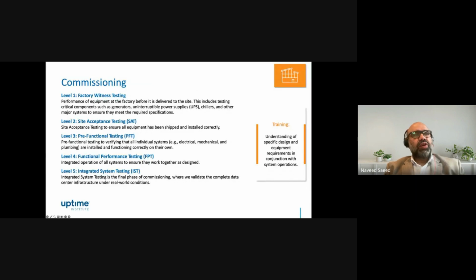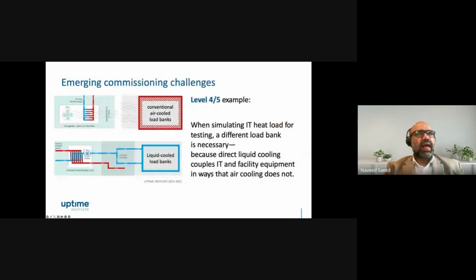Commissioning of these data centers, or recommissioning of a repurposed, retrofitted or upgraded facility, will be different from what we have been doing historically in data centers. So the five levels of commissioning are going to remain the same, but what is required to make it happen will change. For example, for level 4, level 5 commissioning, conventionally air-cooled load banks, as you can see on the diagram above here, were fitted into the racks or on the floor, and they take the cold air from the CRAC units or fan wall units and push the hot air back into the hot aisle containment or hot aisle plenum, returning all the way to the computer room air handling unit or fan wall units. And this is the way the UPSs are fully loaded, the generators are fully loaded, and the power distribution streams are fully loaded at the same time.